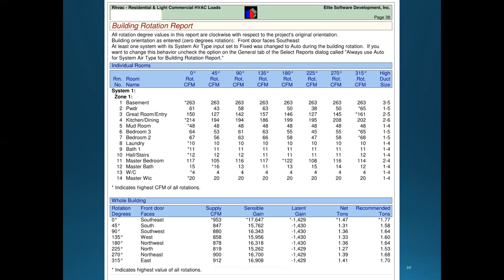In areas with a real latent load, meaning humidity in the air, you're trying to wring the water out of the air, so you'll have a sensible heat ratio that isn't 1. This one's done for Colorado, which is dry as toast, so there's no calculated latent load here. Equipment latent load is 0.